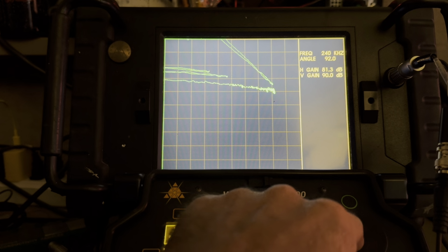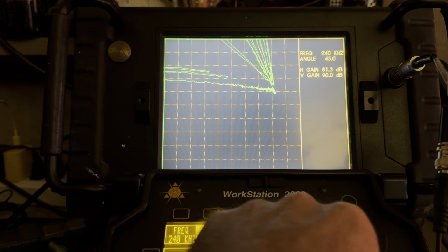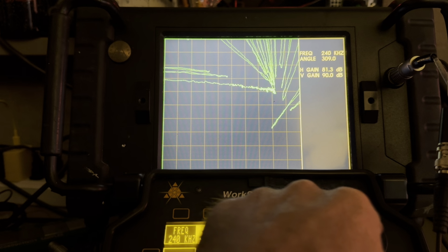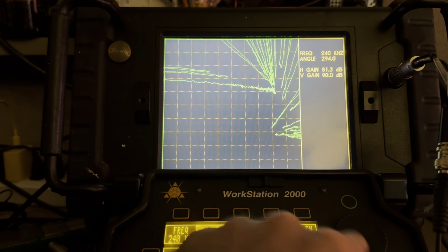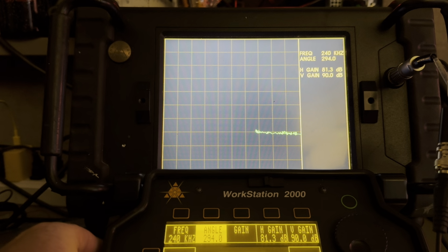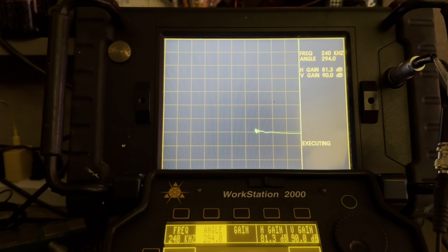I'm just going to tap, tap, tap, like at the dentist when he's checking your filling efficacy. There you go - so that's my air operating point, and my aluminum operating point is off screen to the right. So it's vectored in the right direction, but it's way off screen. All I have to do to remedy that is hit the null button, and that's going to bring my impedance point, my operating point for aluminum, back on the screen. And now I'm just going to move past one of those flaws and see what happens.